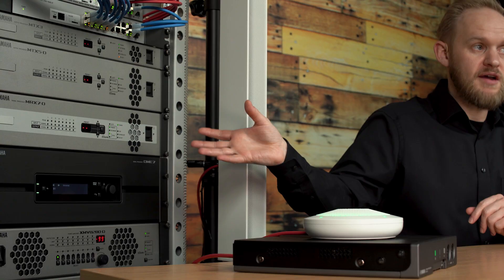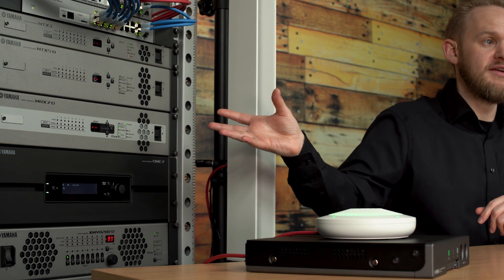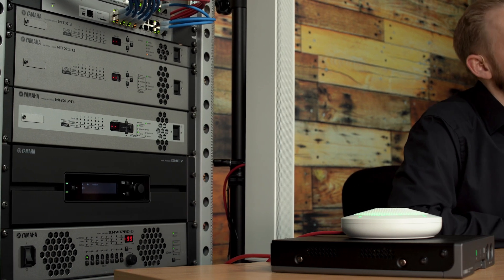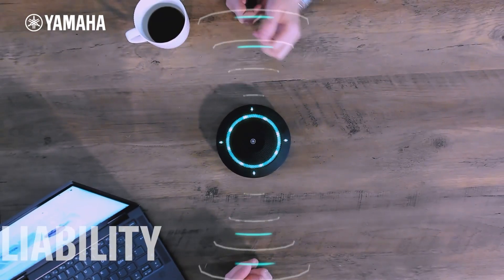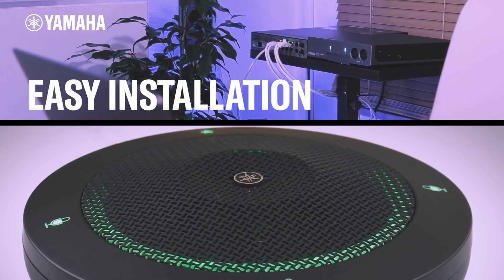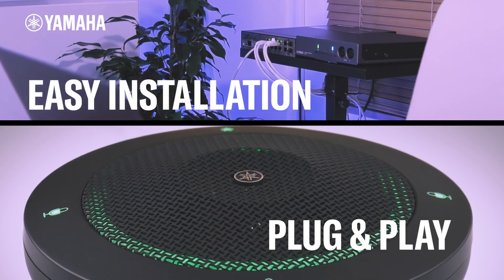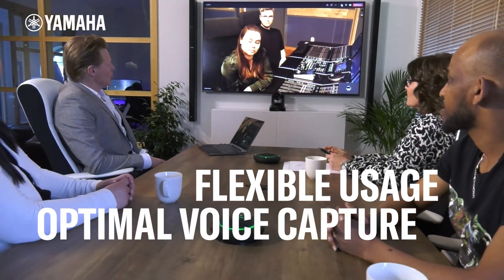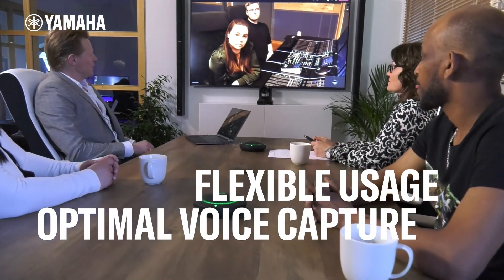However, if you want advanced voicelift capabilities, then you may find yourself combining the RM series microphones with another processor such as the MRX7D or DME7. The RM series microphones are all Dante connected. They have built-in AEC capabilities for conferencing and some advanced processing. However, they also have a second output that runs at lower latency and is designed for voicelift. This channel can be passed into another processor to give the best flexibility.